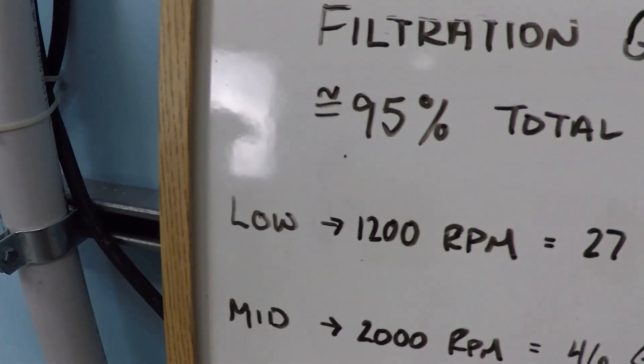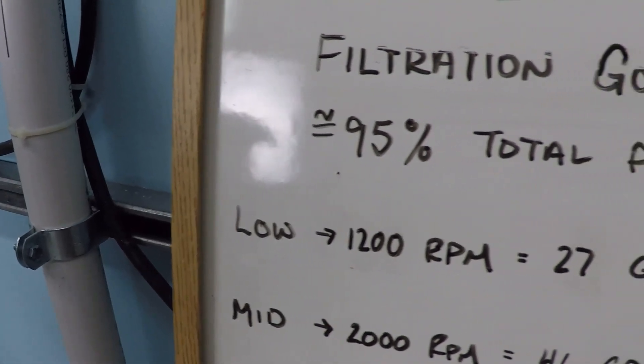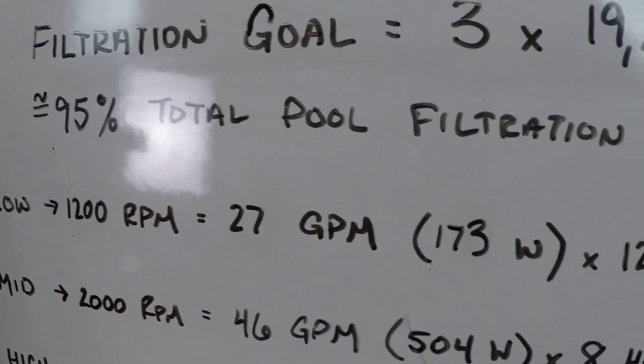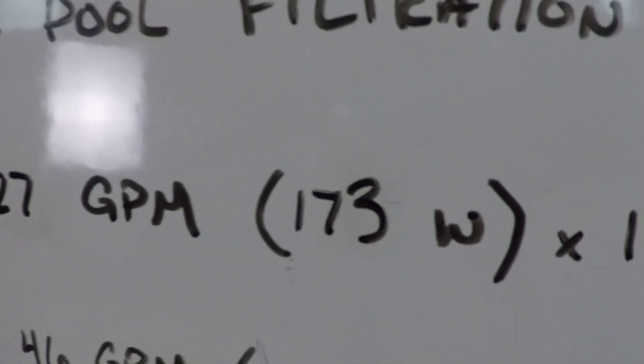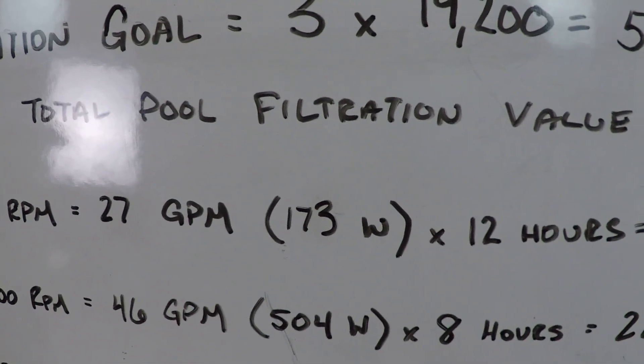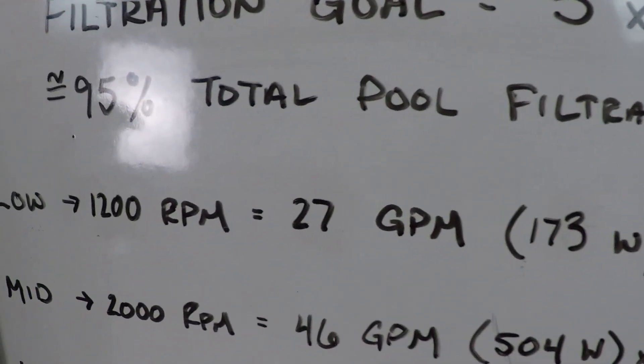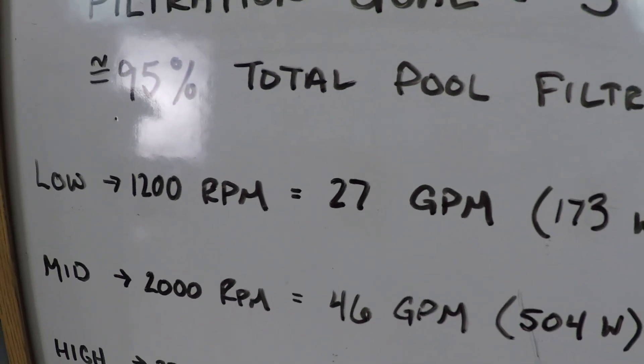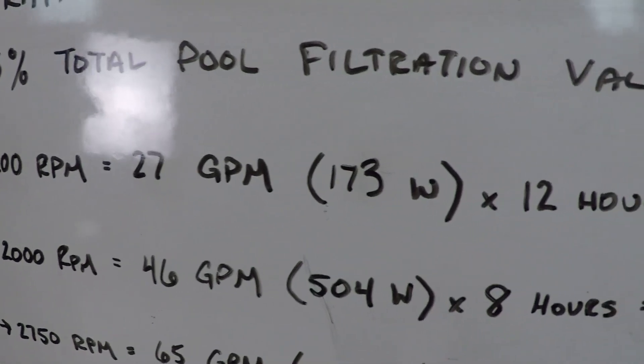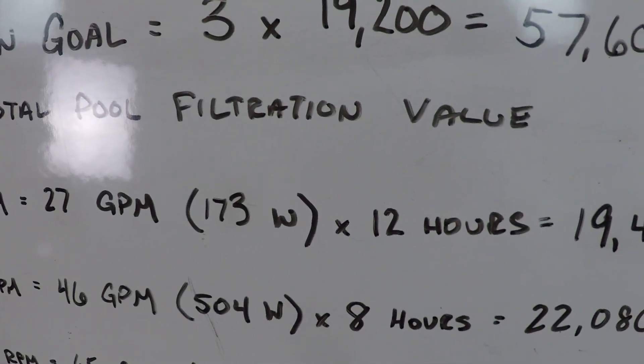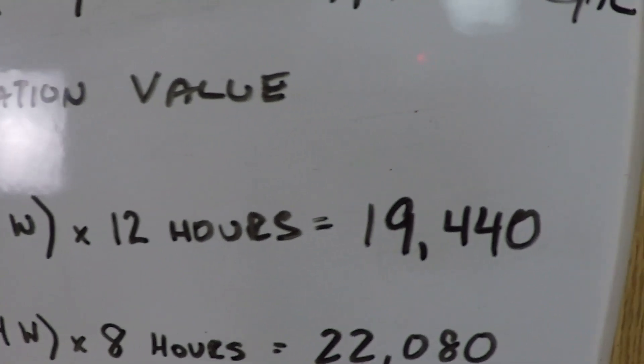You want to run your variable speed pump for long hours per day at low RPM values because of this reason right here. It uses very little power in operating and it still gets a pretty good amount of flow, more than you would think.